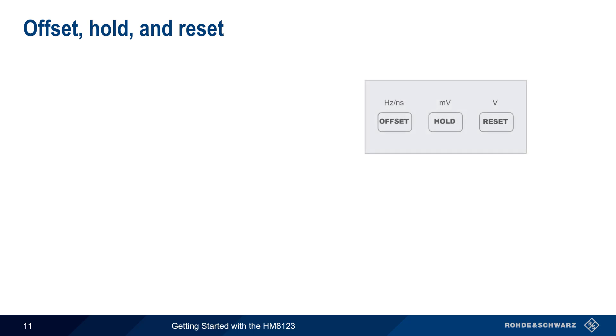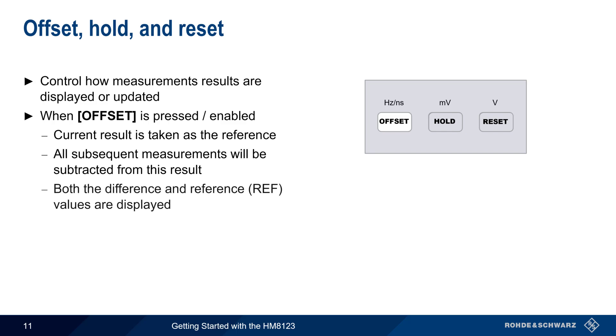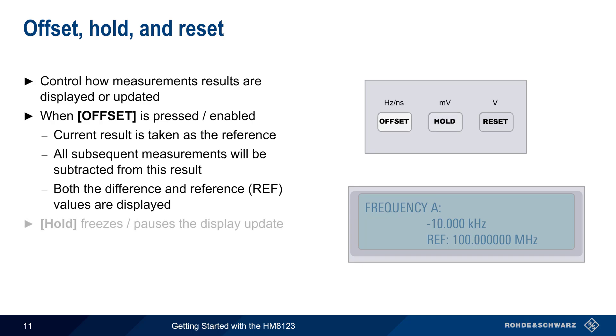The offset, hold, and reset keys control how measurement results are displayed or updated. Pressing the offset key causes the currently measured result to be taken as a reference, and all subsequent measurements will be subtracted from this result. In this case, both the difference as well as the reference values are displayed. The hold key freezes or pauses the update of displayed values. And the reset key clears and restarts the total count measurements that we looked at earlier.